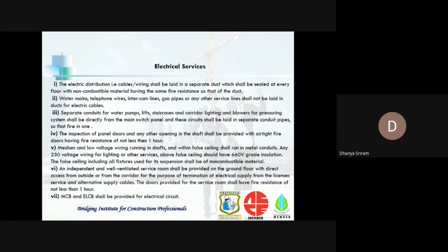An independent and well ventilated service room shall be provided on the ground floor with direct access from the outside or from the corridor, for the purpose of termination of electrical supply from the licensed service and alternative supply cables. The doors provided for the service room shall have a fire resistance of not less than 1 hour. MCB and ELCB shall be provided for electrical circuits. The main chamber will be provided on the ground floor for easy access.